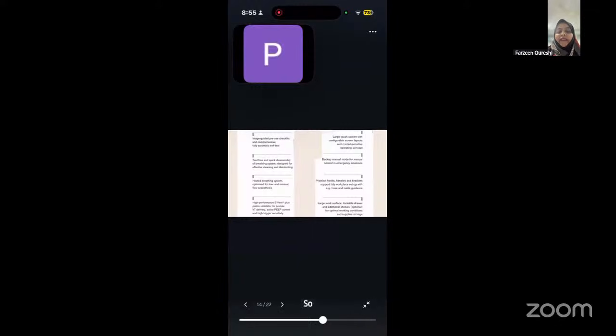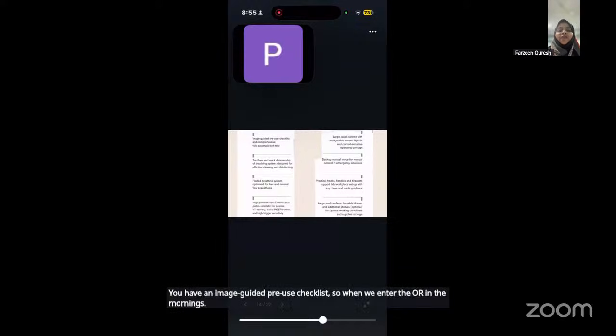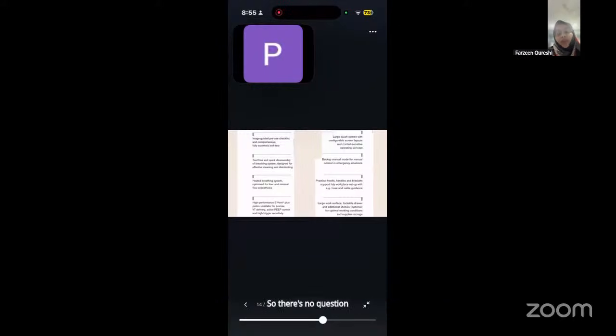So you have a heated breathing system, you have a tool-free and quick disassembly of the breathing system, you have an image-guided pre-use checklist. So when we enter the OR in the mornings, we have an image-guided checklist. So even if I'm not able to read, I can see the image and I can check. And unless I pass my checklist every morning, I cannot start my anesthesia workstation. It's as simple and as direct as that. So there's no question of I didn't check, you didn't check, he didn't check. It will not start unless you check.